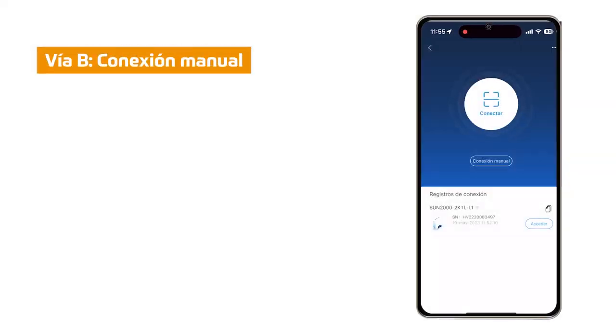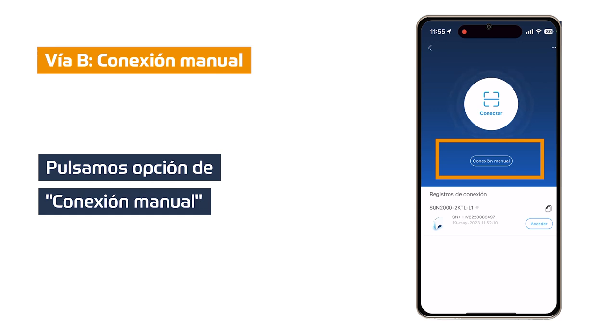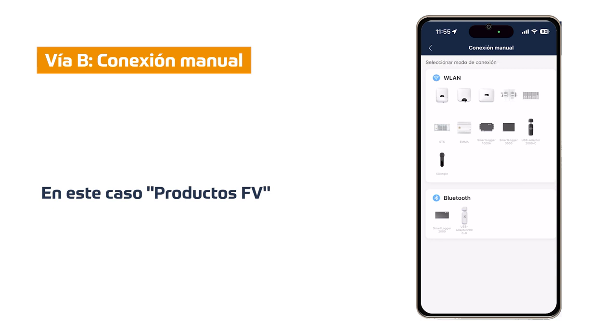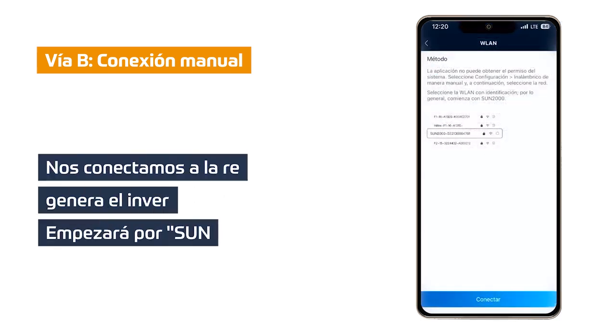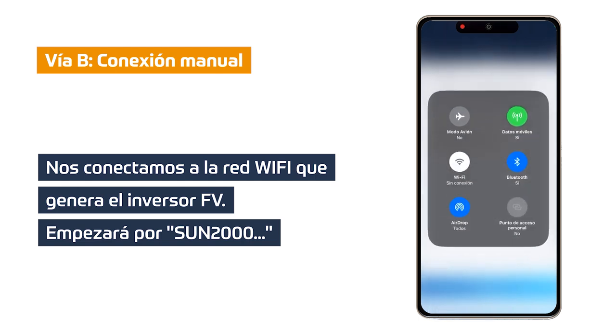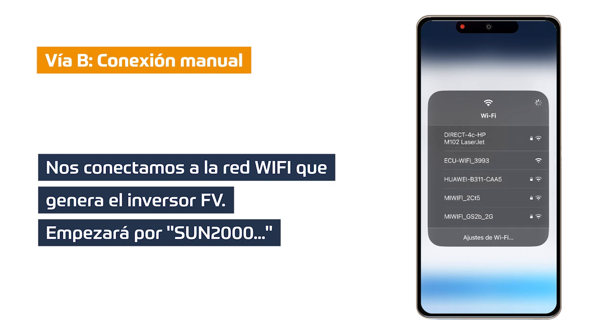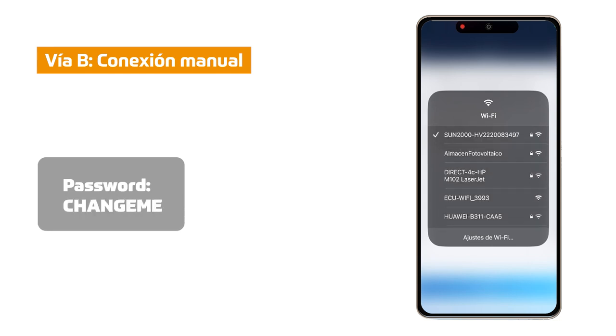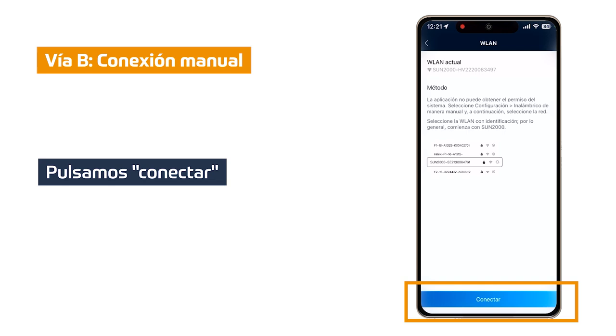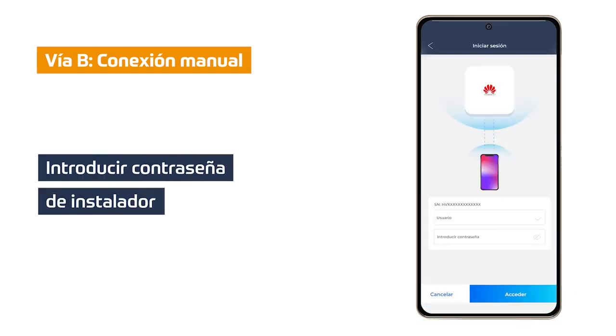Way B: We click on WLAN manual connection and configure the current LAN of our mobile device. We choose the device we want to modify its Wi-Fi network, which in this case will be FV products as it is an inverter. We must connect to the WLAN network of the inverter, which will start with SUN2000. We click on configure, activate our Wi-Fi and look for the SUN2000 network. Click on it and wait for it to connect. If it asks for a password, it will be CHANGEME (C-H-A-N-G-E-M-E). We go back and click connect. In this case we must enter the installer password.